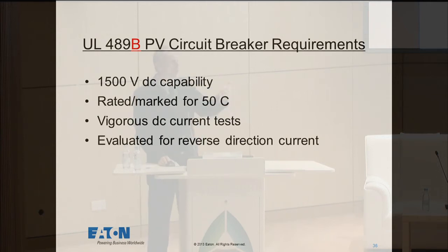And they are also rated, evaluated, and marked for 50 degrees C, because we know that that's very important, the elevated ambient in these applications. So this is something very unique, 50 degrees C applications. And there are vigorous test programs included in the document for the DC testing, the overload, the short circuit, everything you have to do. And one of the big considerations for photovoltaic applications is you now have current going in the reverse direction. So it's something different here. But that is the quick summary of what's important for PV circuit breakers.